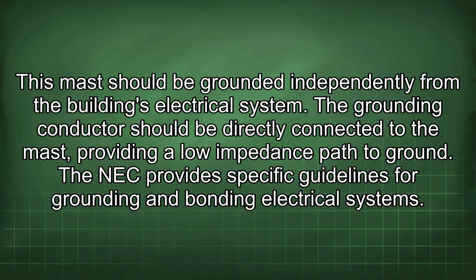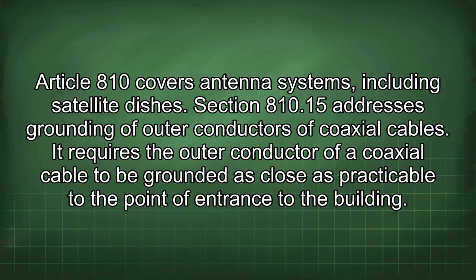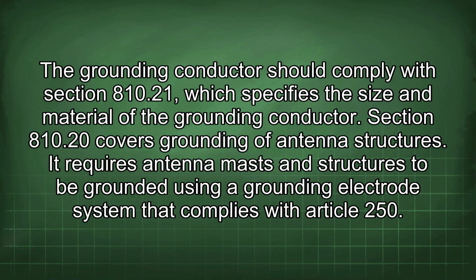The NEC provides specific guidelines for grounding and bonding electrical systems. Article 810 covers antenna systems, including satellite dishes. Section 810.15 addresses grounding of outer conductors of coaxial cables. It requires the outer conductor of a coaxial cable to be grounded as close as practicable to the point of entrance to the building. The grounding conductor should comply with Section 810.21, which specifies the size and material of the grounding conductor. Section 810.20 covers grounding of antenna structures.